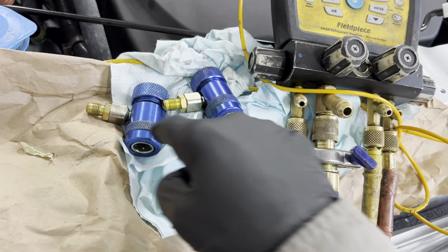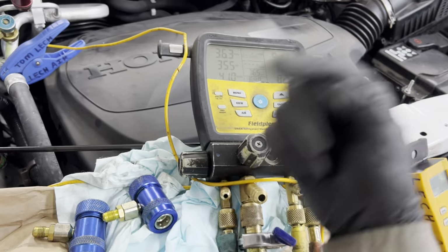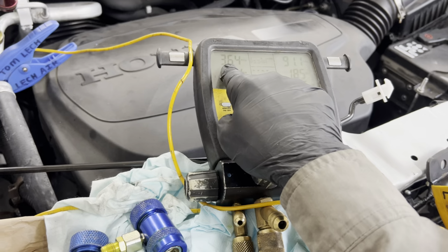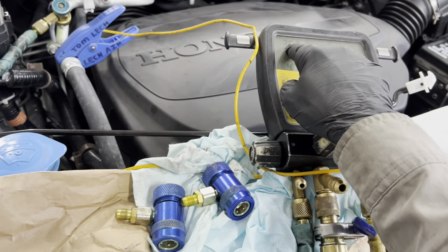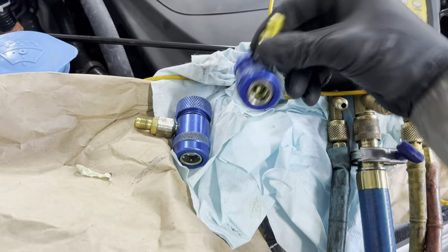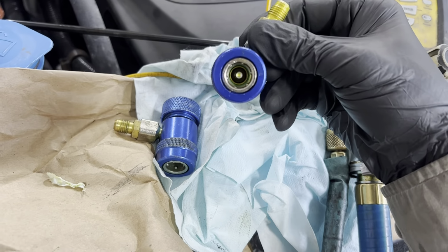Right, I changed out the fitting. That was the problem from the last video. Remember, we had about 64 PSI here. We had 64 PSI because the depressor down in there was not hitting the pintle, the valve core in the middle, depressing it, allowing us to correctly read our suction line.